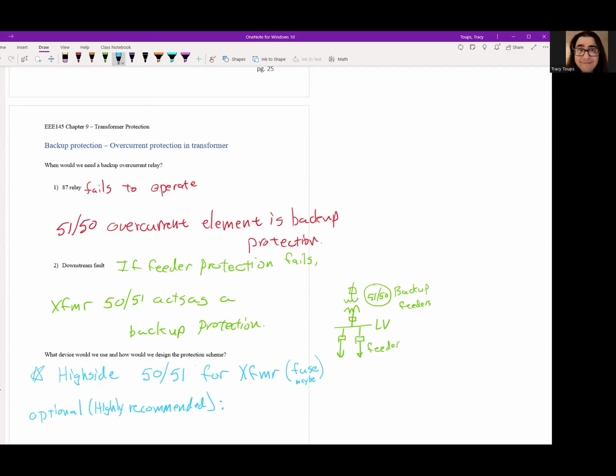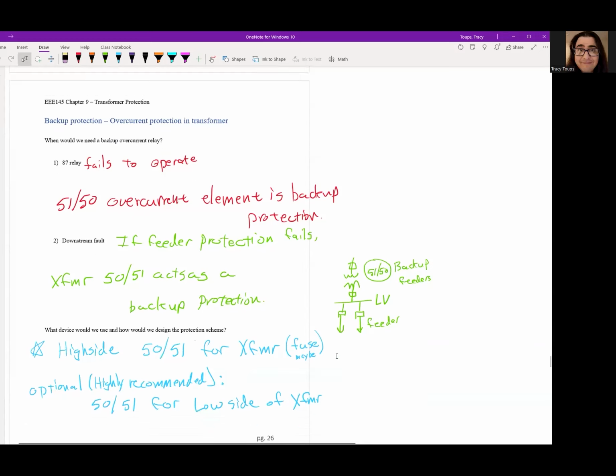is a, let me write down here, 50-51 for the low voltage side. Some utilities cheap out on this one, some don't, but you really should have that 50-51 on the low side of the transformer because that's the relay that protects the feeders. Okay, so ideally you should have one on both sides of the transformer. If you cut corners, just put it on the high side, but have something on the high side. Okay.